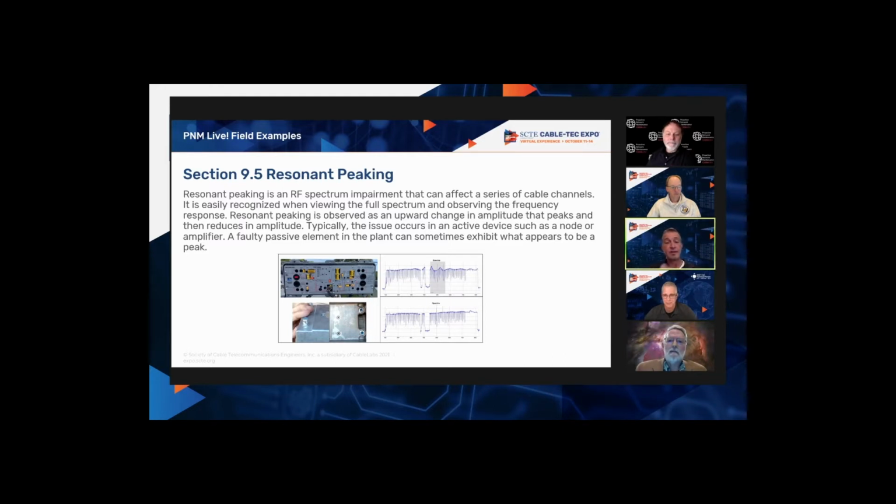And you saw in the previous example where I was out there with Dave, the meter could see that resonant peak, that peaking energy, and it just destroyed the performance of the carrier. The MERs were unusable at the magnitude of the peak. And more than one peak here.